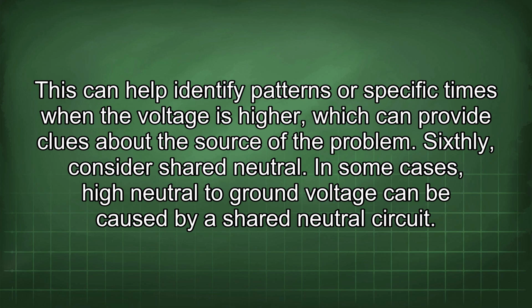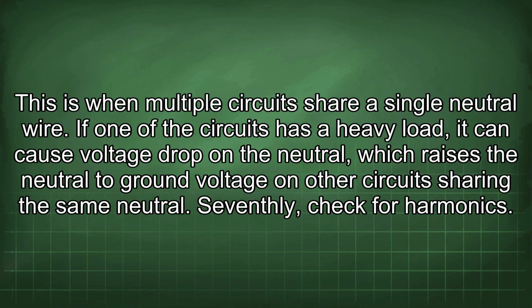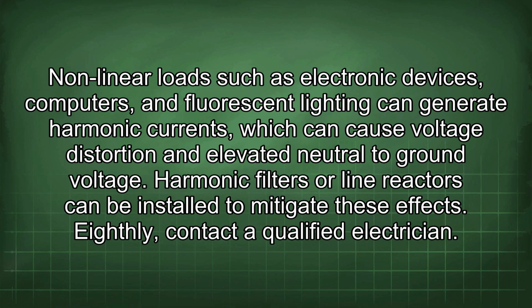Sixthly, consider shared neutral. In some cases, high neutral to ground voltage can be caused by a shared neutral circuit. This is when multiple circuits share a single neutral wire. If one of the circuits has a heavy load, it can cause voltage drop in the neutral, which raises the neutral to ground voltage on other circuits sharing the same neutral. Seventhly, check for harmonics. Nonlinear loads such as electronic devices, computers, and fluorescent lighting can generate harmonic currents, which can cause voltage distortion and elevated neutral to ground voltage. Harmonic filters or line reactors can be installed to mitigate these effects.